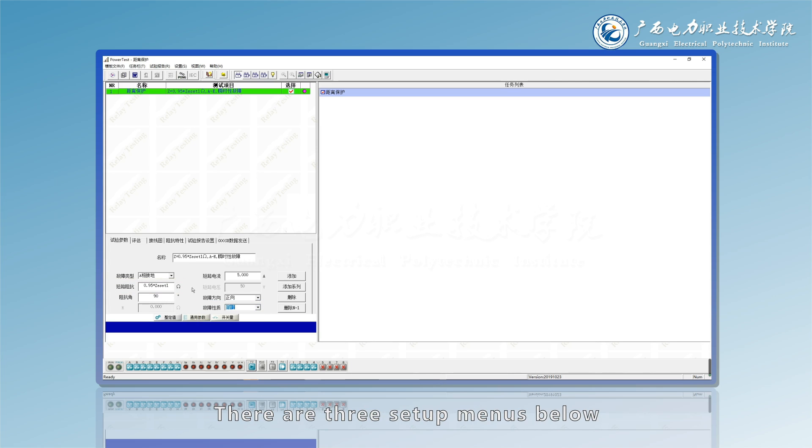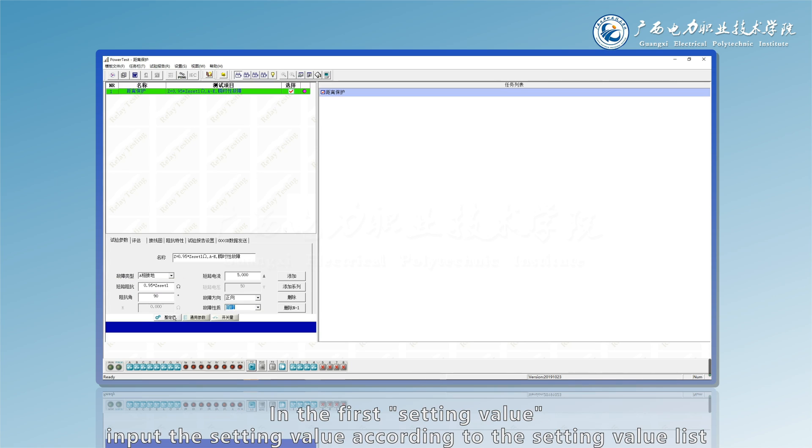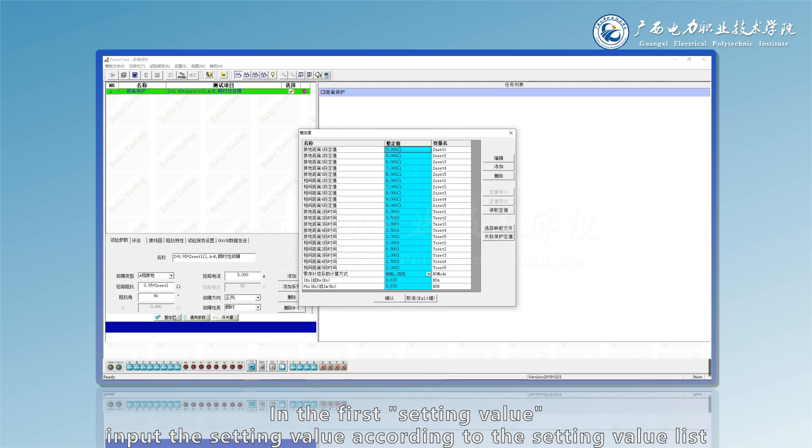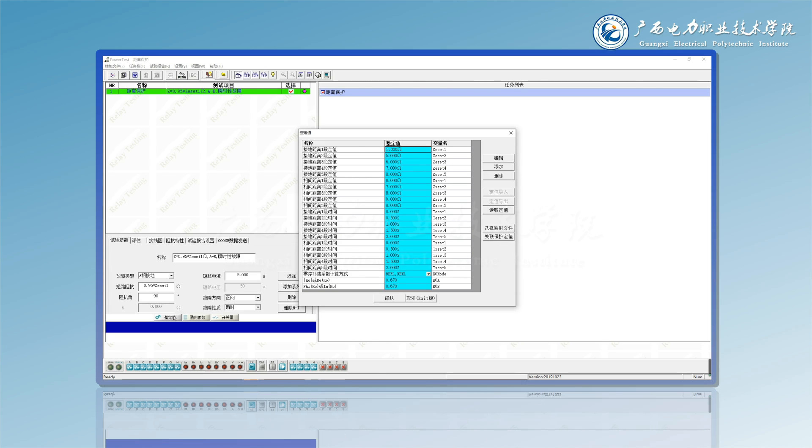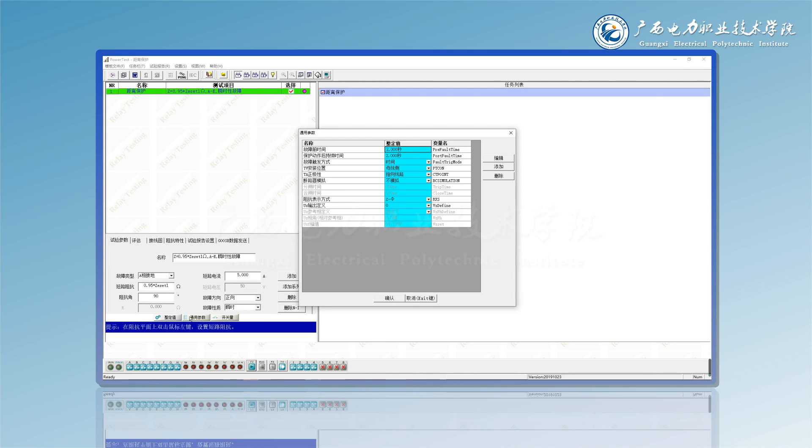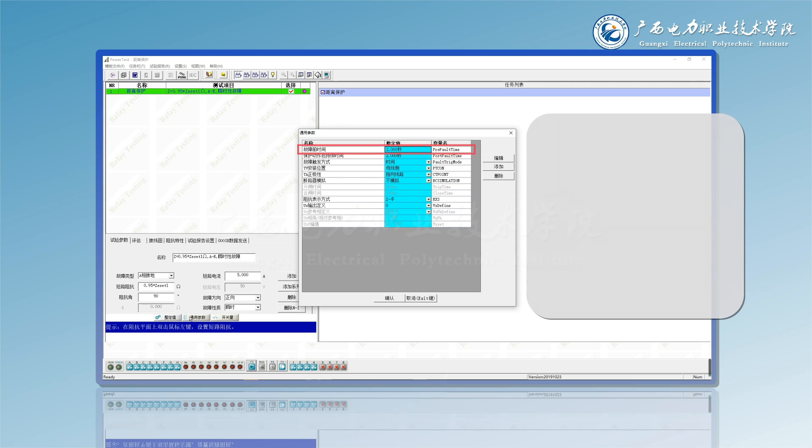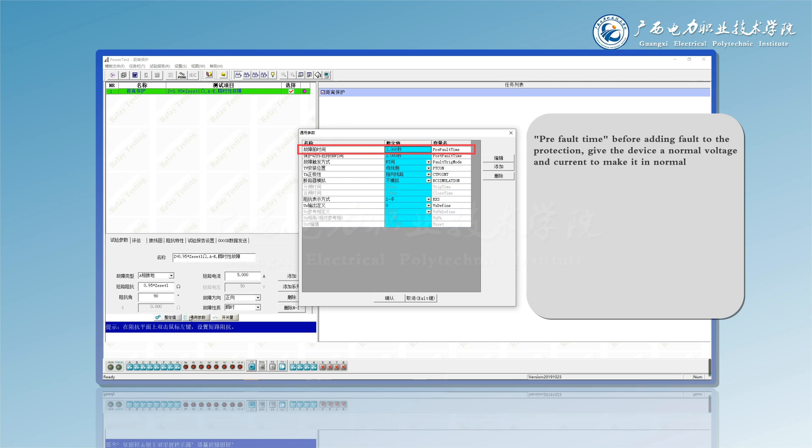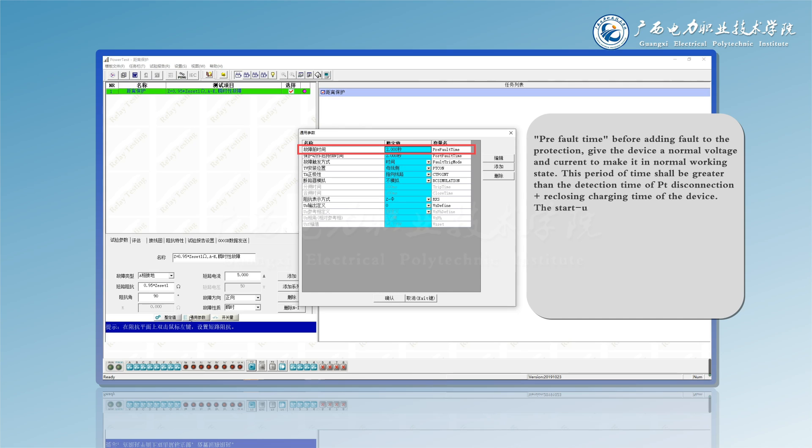There are three setup menus below. In the first setting value, input the setting value according to the setting value list. In the second general parameters, there are two main time settings. Pre-fault time: before adding fault to the protection, give the device a normal voltage and current to make it in normal working state. This period of time shall be greater than the detection time of Pt disconnection plus reclosing charging time of the device.